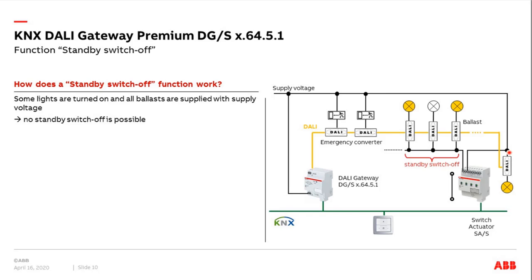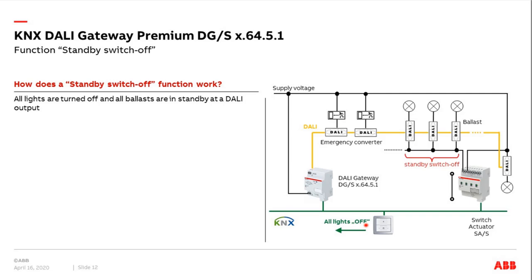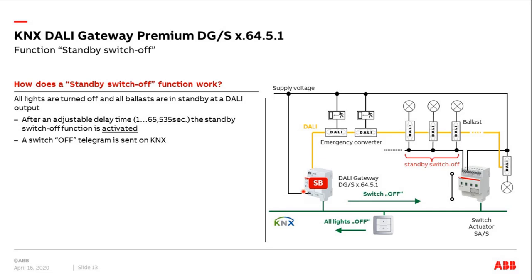In principle, it makes sense to switch the supply voltage of all the ballasts. When some lights are on, the standby switch-off function cannot be activated. When we press the rocker and switch off all the lights — all 64 ballasts are now switched off — then after a delay time adjustable in the ETS parameters (for example between 1 and 65,000 seconds, which is about 18 hours), the DALI gateway activates the standby switch-off function.